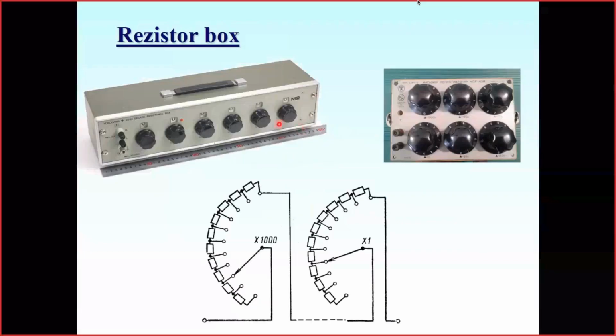About the resistor box itself. As I said, this is actually what these resistor boxes are: some kind of working etalons, or measures. And these etalons usually have a very good accuracy class. The accuracy class may be 0.1 or 0.2, which means that the accuracy of the set resistance doesn't exceed 0.1% of the set resistance. So it's not so bad.